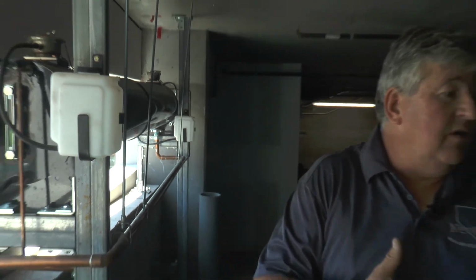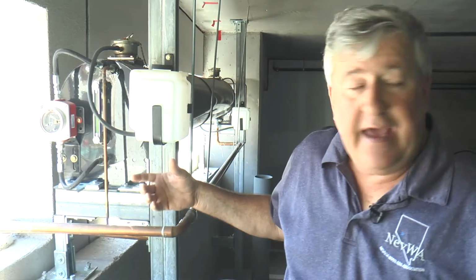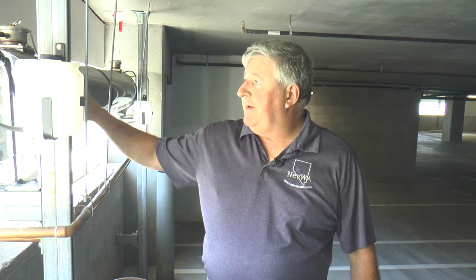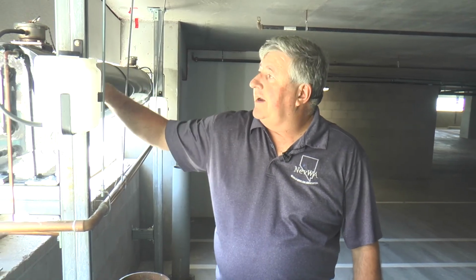and if we go through and do quarterly inspections and stuff like that, we can provide a coolant top-off service. It will burp some coolant because there's probably air bubbles in the system that just haven't migrated their way out. So as that coolant level comes down, just keep an eye on the level, and when it gets low, coolant goes in it. That's basically about it. If you don't see it all over the floor downstairs, it's just equalizing. Expansion tank, in the event that the thermal expansion downstairs causes the water to expand, it's going to collect in here. Whatever it can't hold here, it'll bleed off into the tank, just like your automobile.